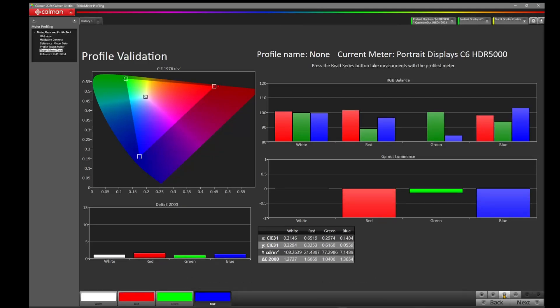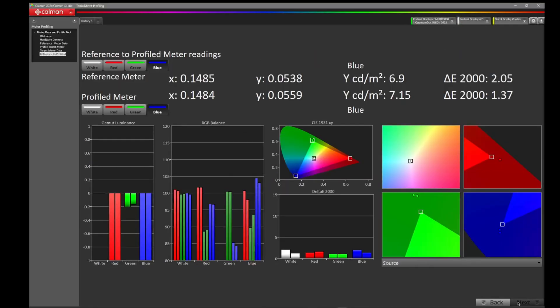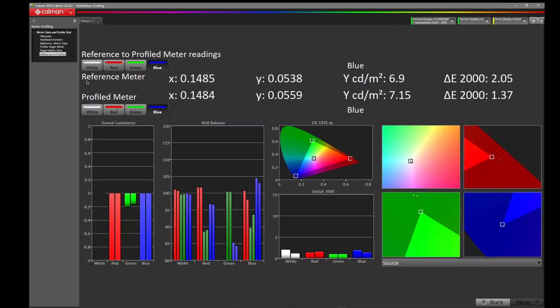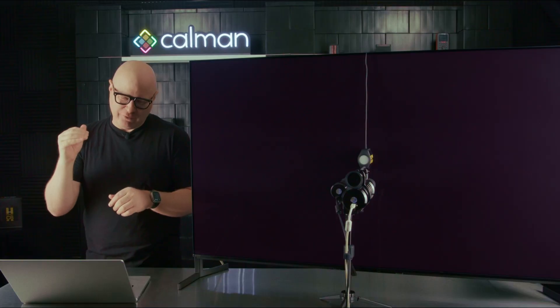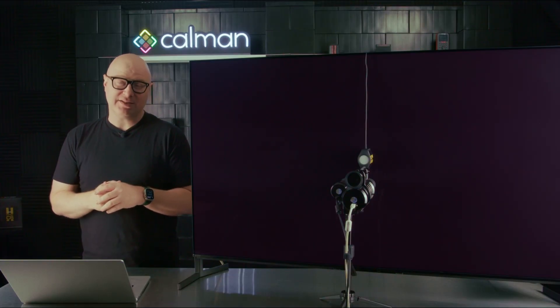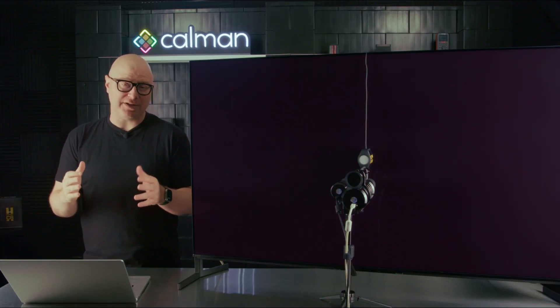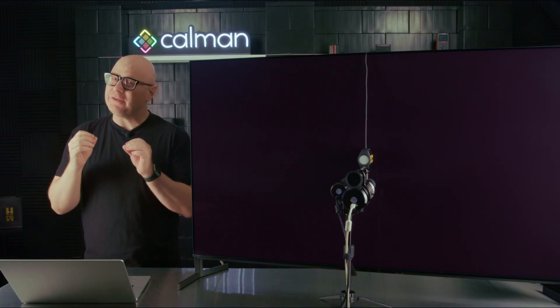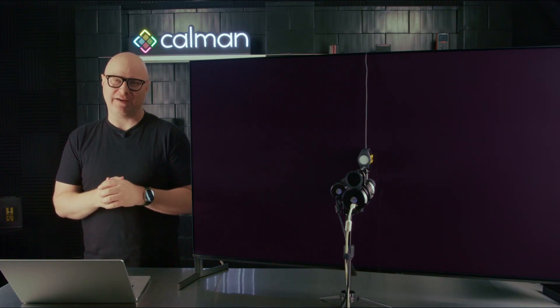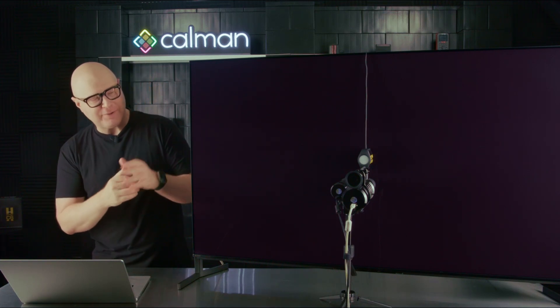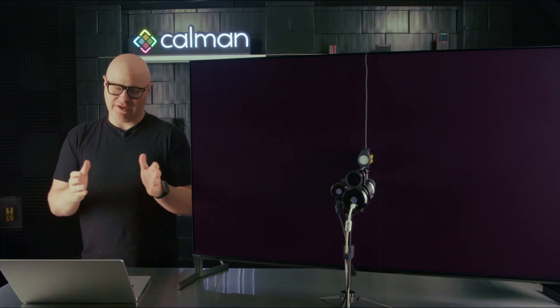So with our meter profile loaded on the C6 HDR5000, we're now going to hit Read Series in the bottom right and allow that to perform its measurement. The profile validation has completed. Now we want to compare our two meters and see how they performed. Let's come to the bottom right and press Next. On this page, you'll notice we now have our reference to profile meter readings with our reference meter here on the top left and the profile meter on the bottom left. We're comparing the built-in profile that ships with every C6 HDR5000 to the Colorimetry Research CR300.